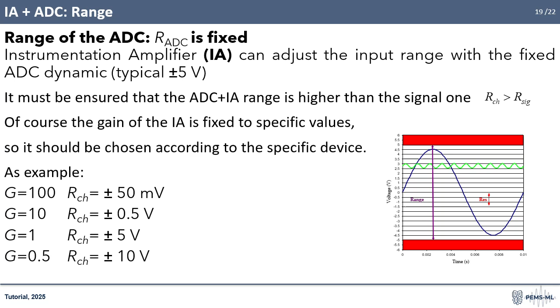Here you can find some examples of typical gains that can be set for the instrumentation amplifier, as well as the relative range of the channels. For a gain equal to 100, the range is set to plus or minus 50 millivolts, so the input signal should be lower than 50 millivolts. The gain should be chosen as close as possible to the input dynamics to increase the resolution of the digital signal, namely, to decrease the quantization error.